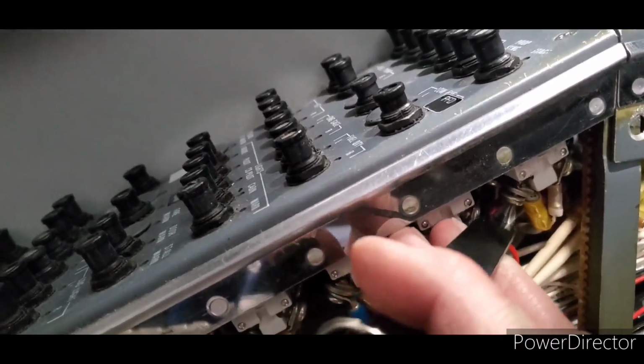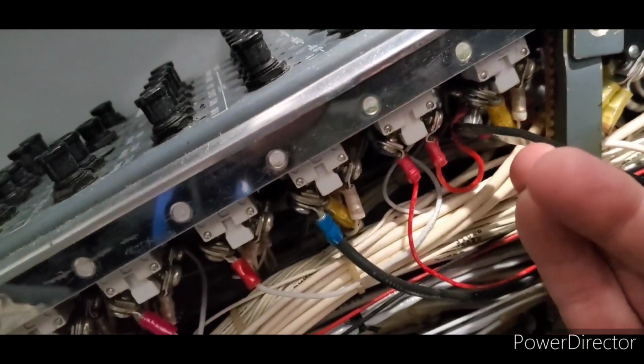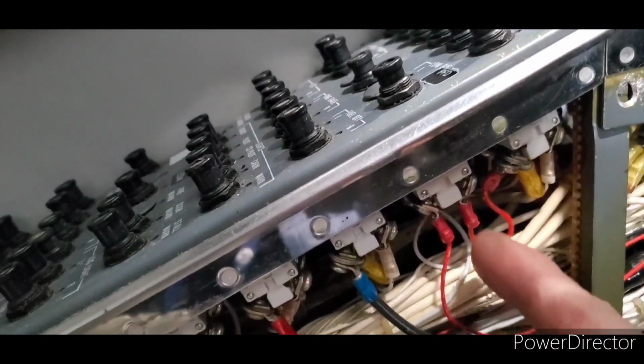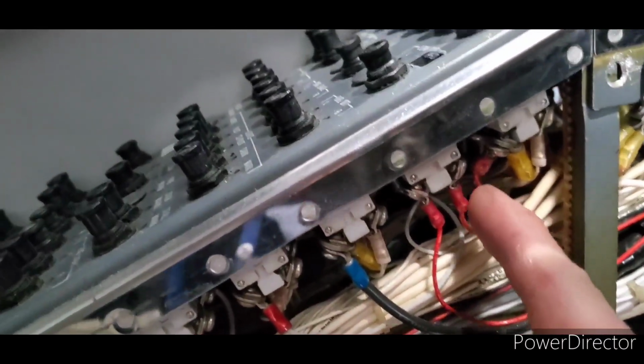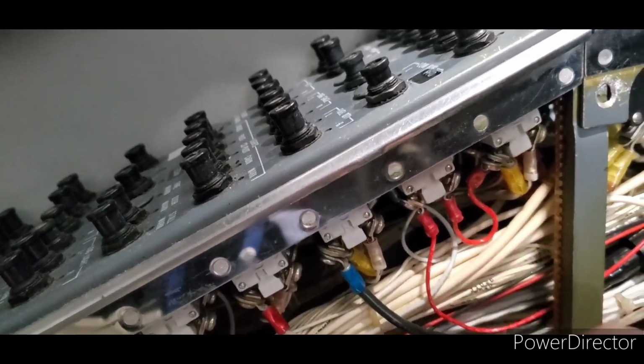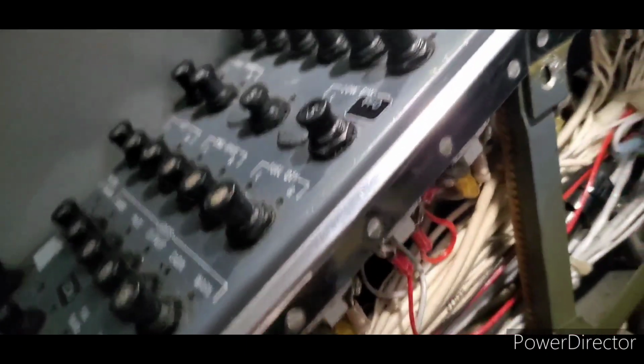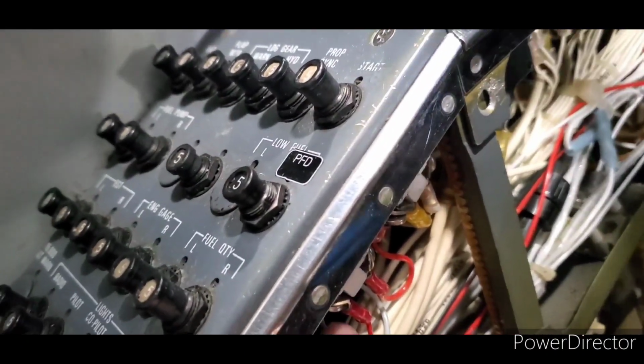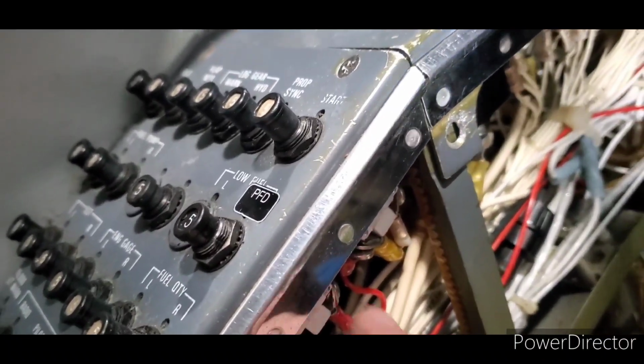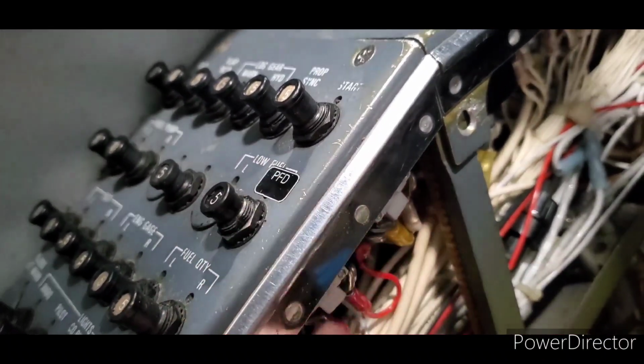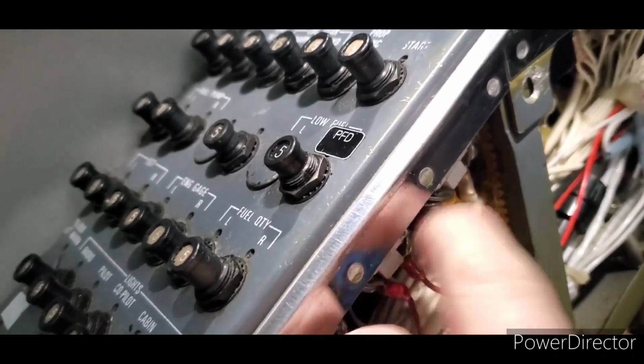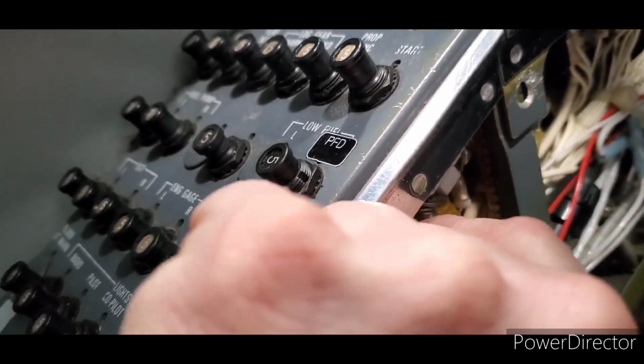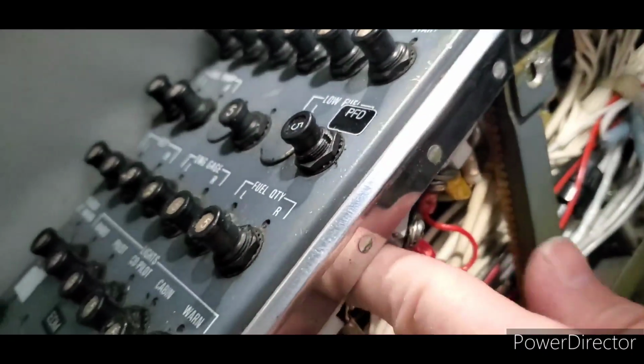And can tighten up this screw the way we want, and we'll have the wire routed correctly and the terminals going correctly. And then one other thing we're going to have to check is the circuit breaker itself, tight that this is connected to. And if you can see, yeah, it's not. That circuit breaker is very loose.